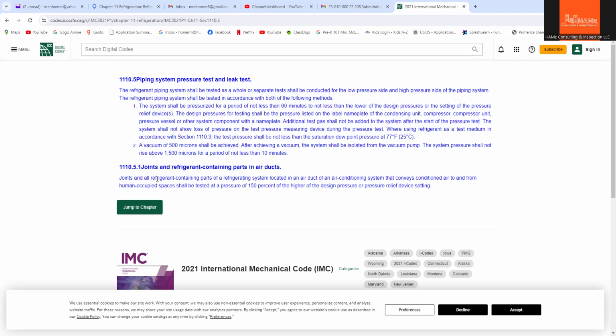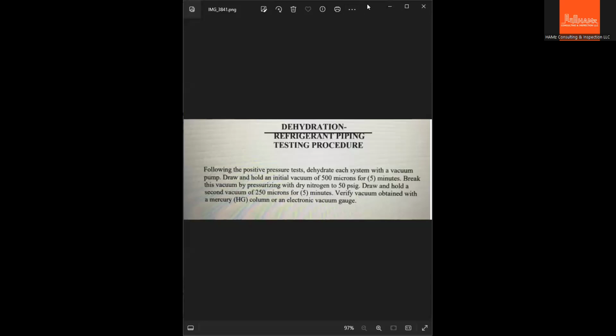This is another thing for reference. If your refrigerant piping is running in the air duct, this is more restrictive. You have 150% of the pressure to be applied during the test. This pressure will be applied on the higher of the design pressure line or the pressure relief device. So, another requirement I have encountered on the job, if ever you encounter it also and you don't have the correct people to provide it to you.